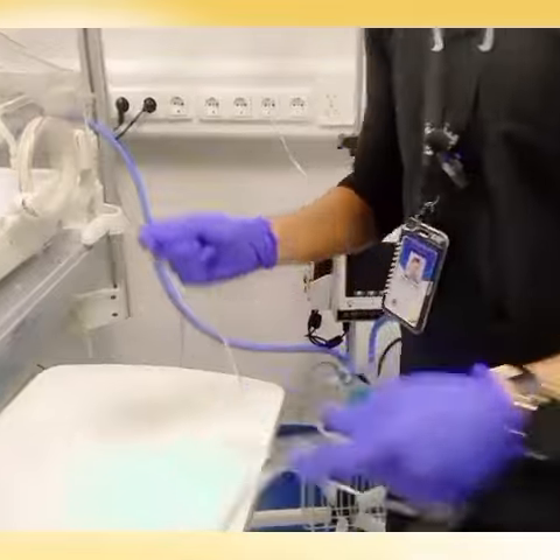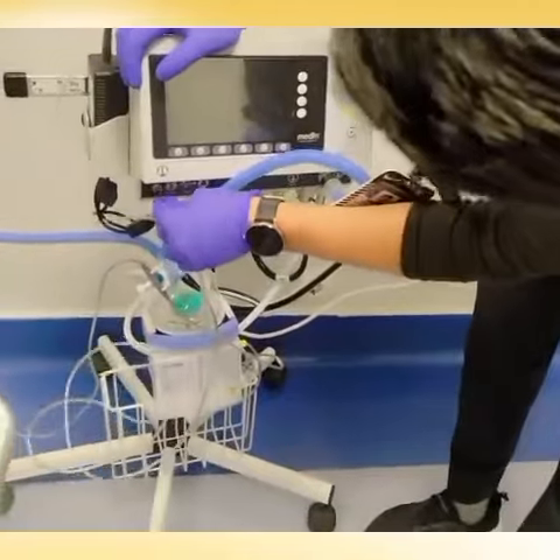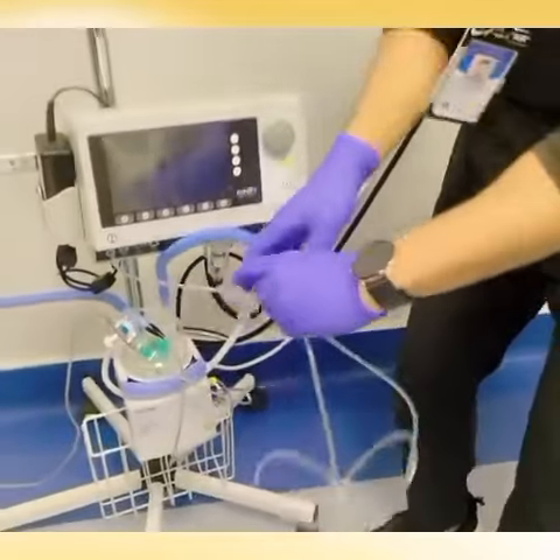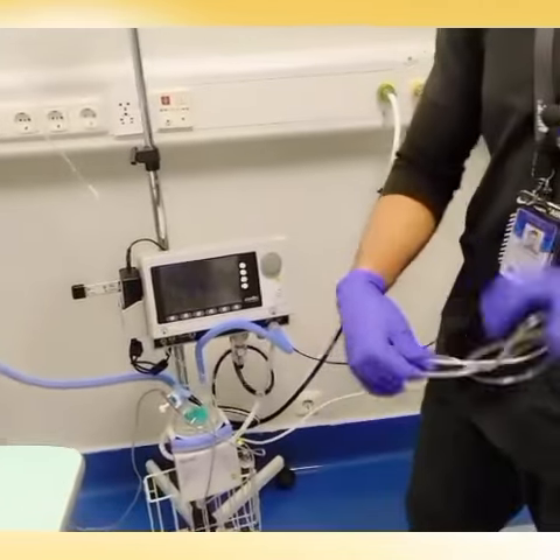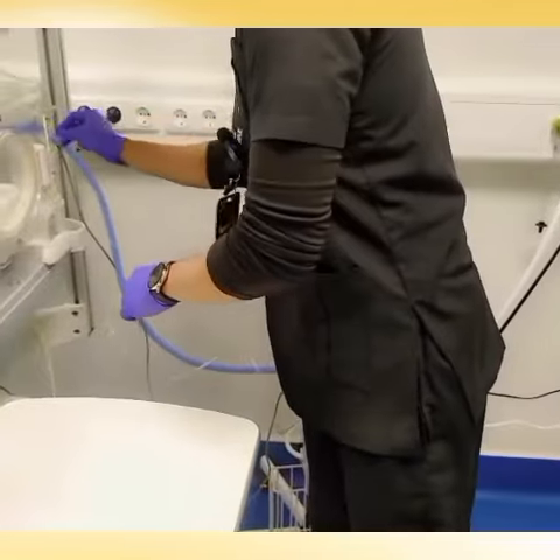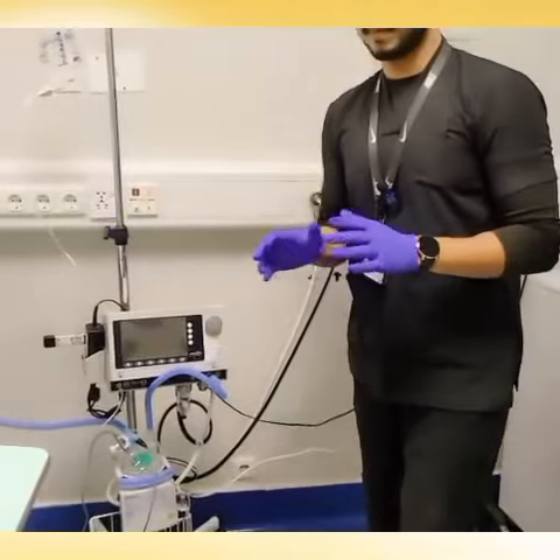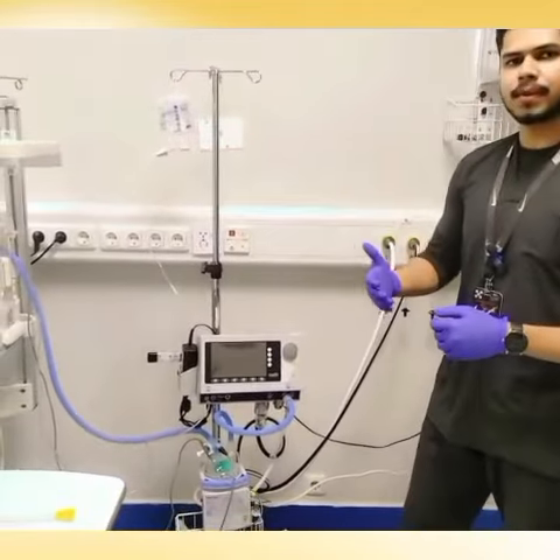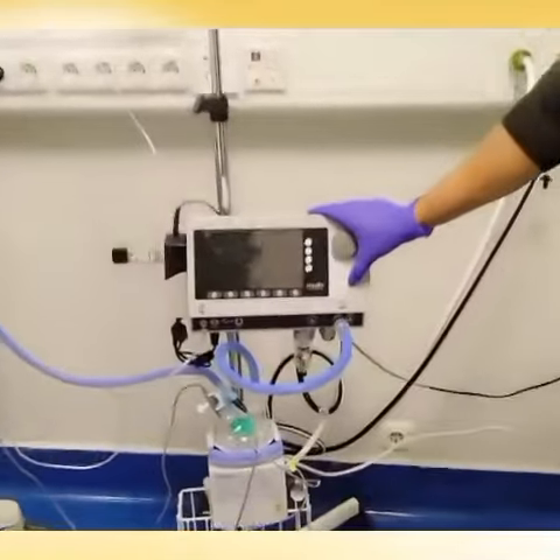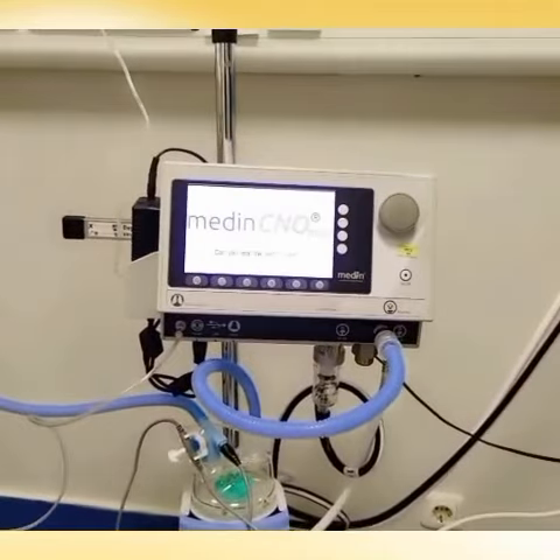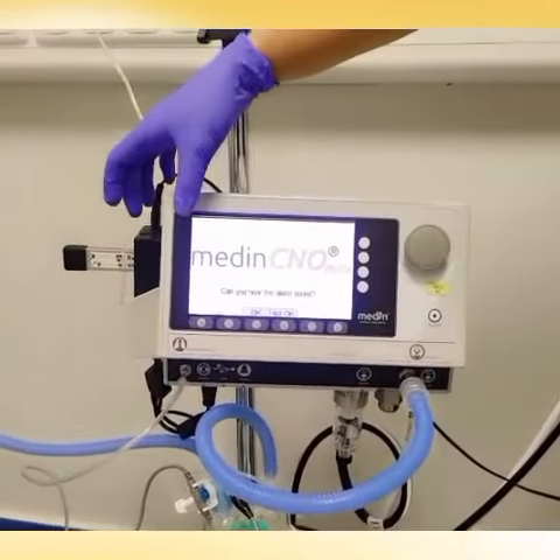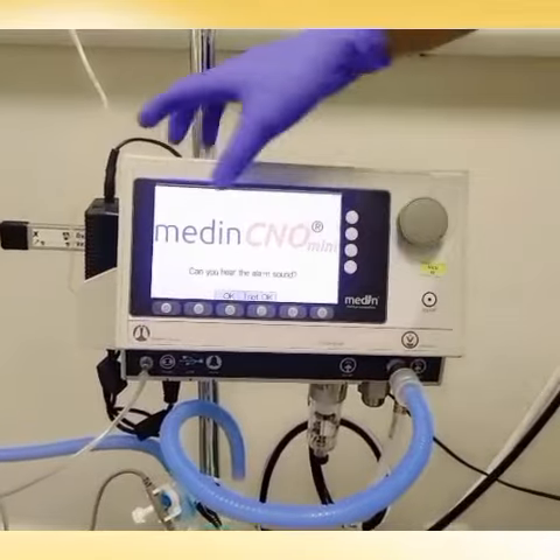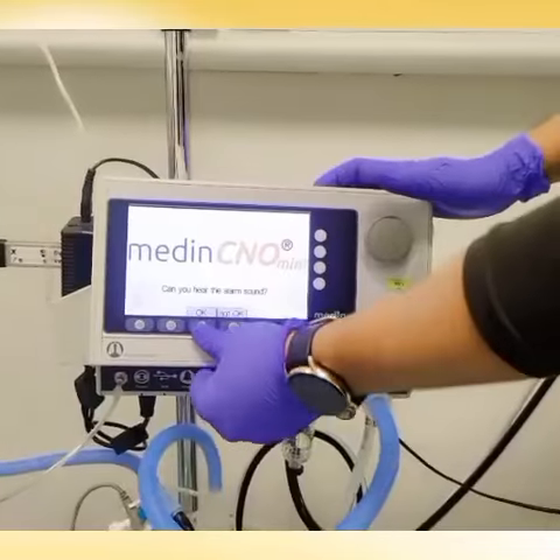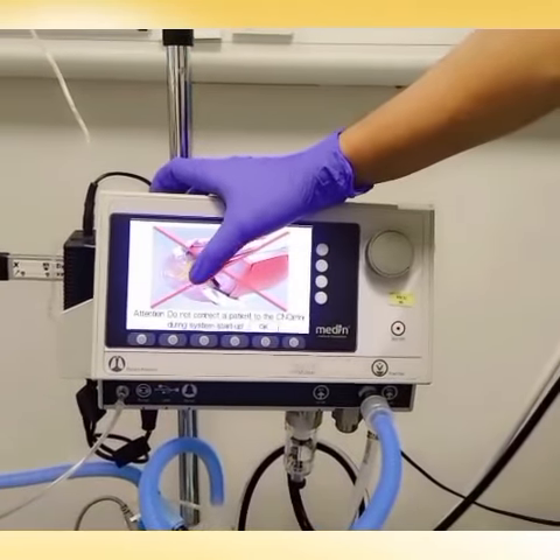Last but not the least, we have the pressure line that goes in here and goes to the patient side. That will connect with the generator. Okay, fine. So the next step is device calibration. Here's the on and off button. Now for calibration, we have to follow the instructions that the device will give us. Okay, here, can you hear the alarm sound? We can hear the alarm sound. Okay. Do not connect a patient to the CNO during system startup.